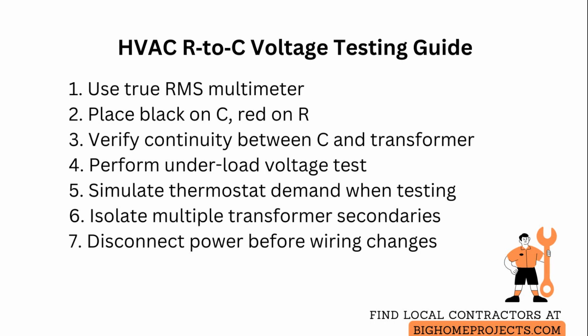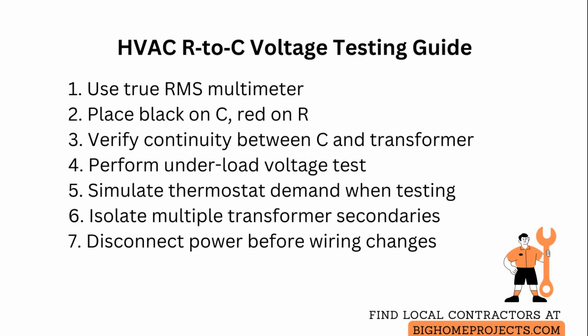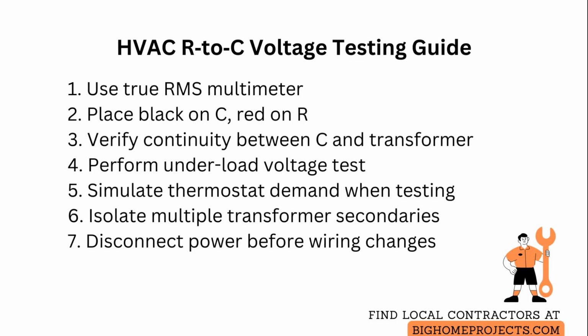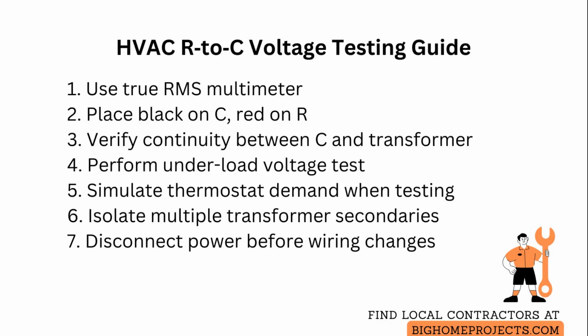Under-load testing can reveal marginal transformers that read high with no load. Simulate thermostat demand by momentarily shorting R to W through a resistor or use a known working controller to draw current and confirm voltage remains within the specified range.